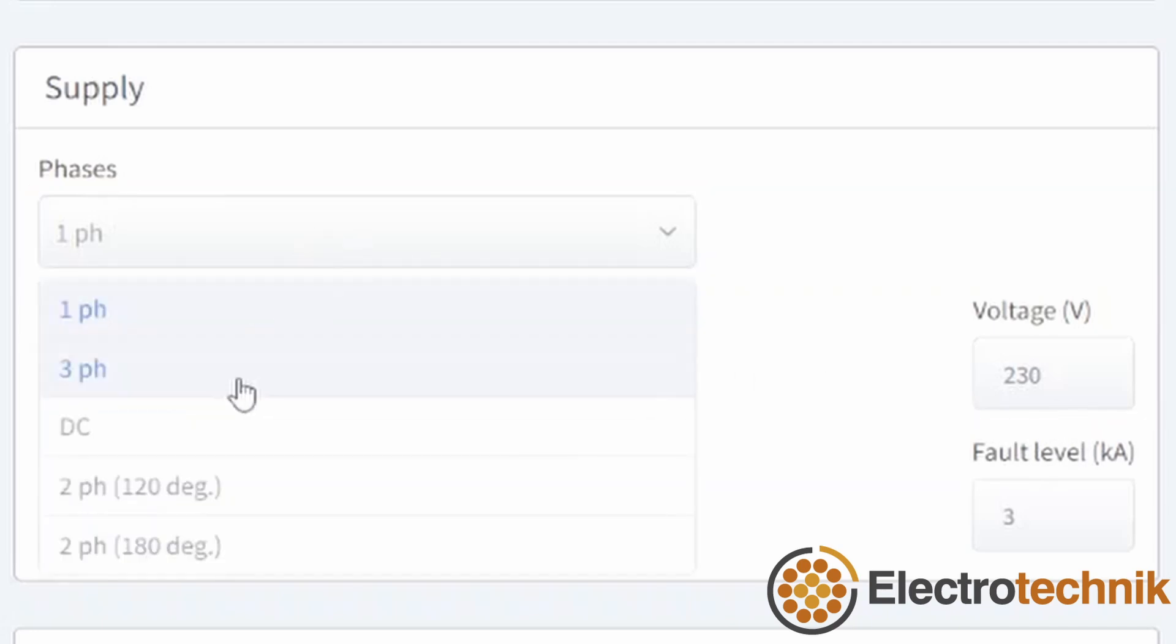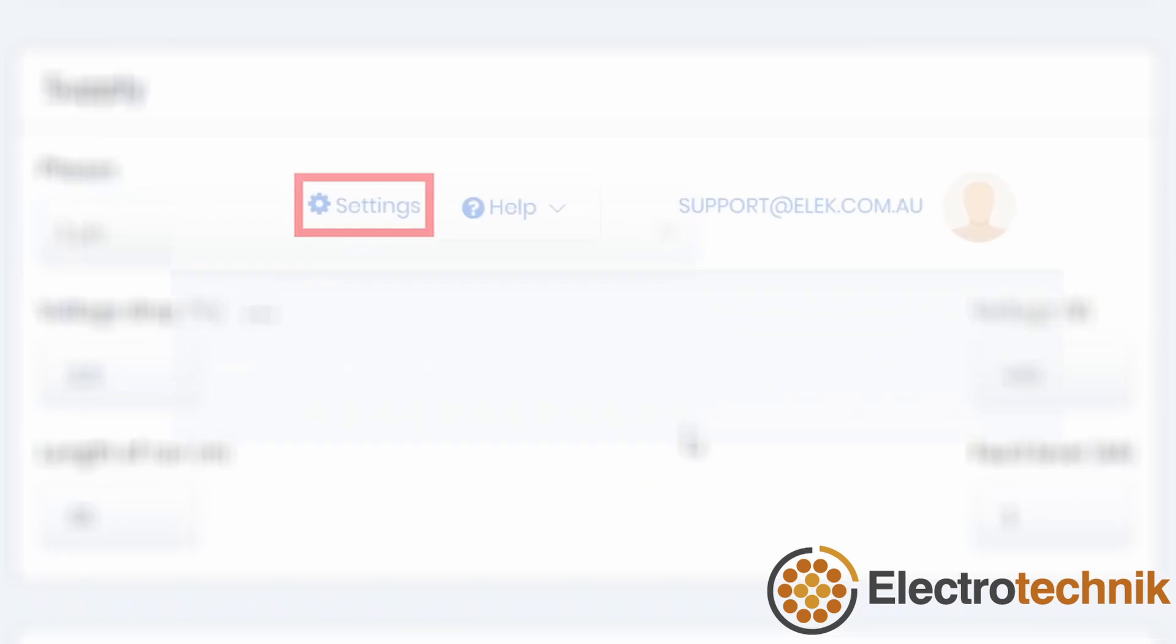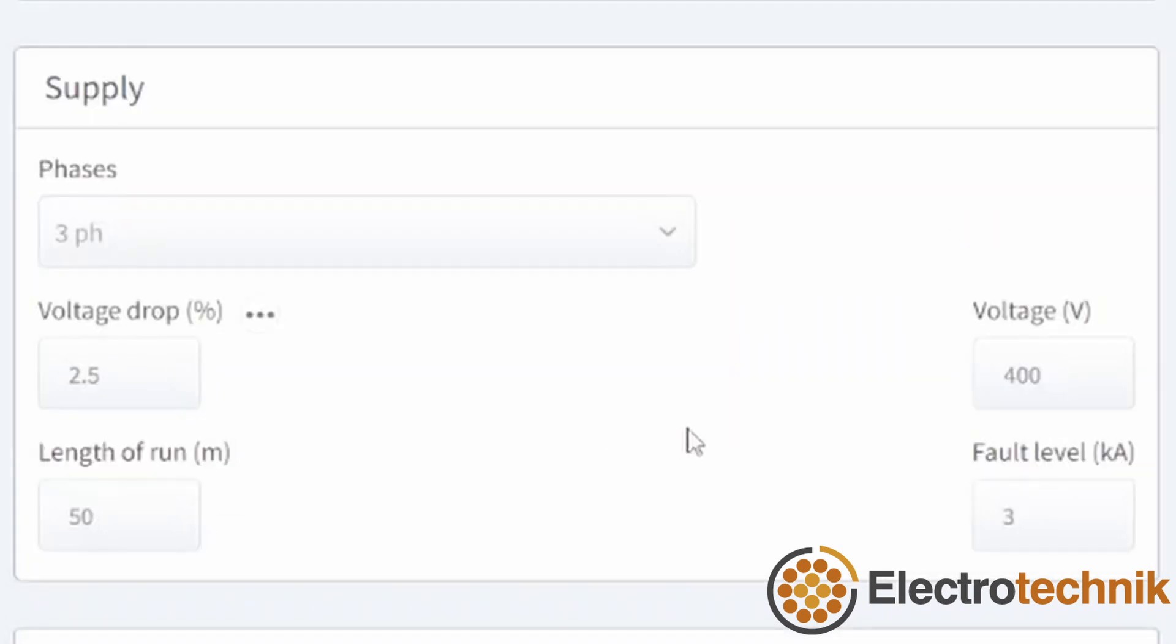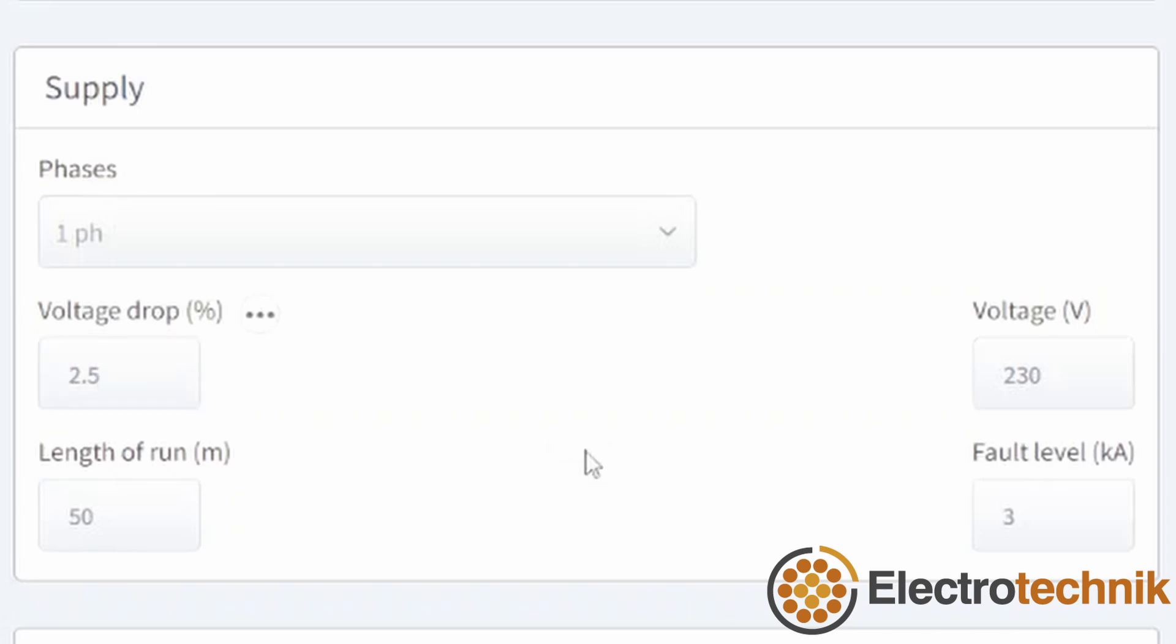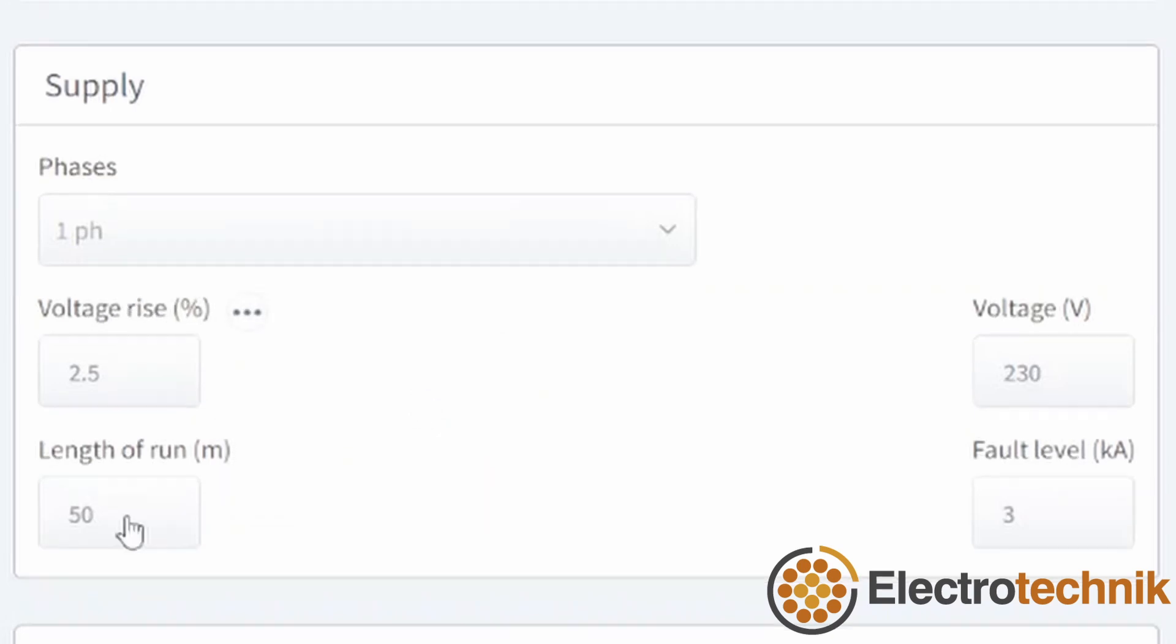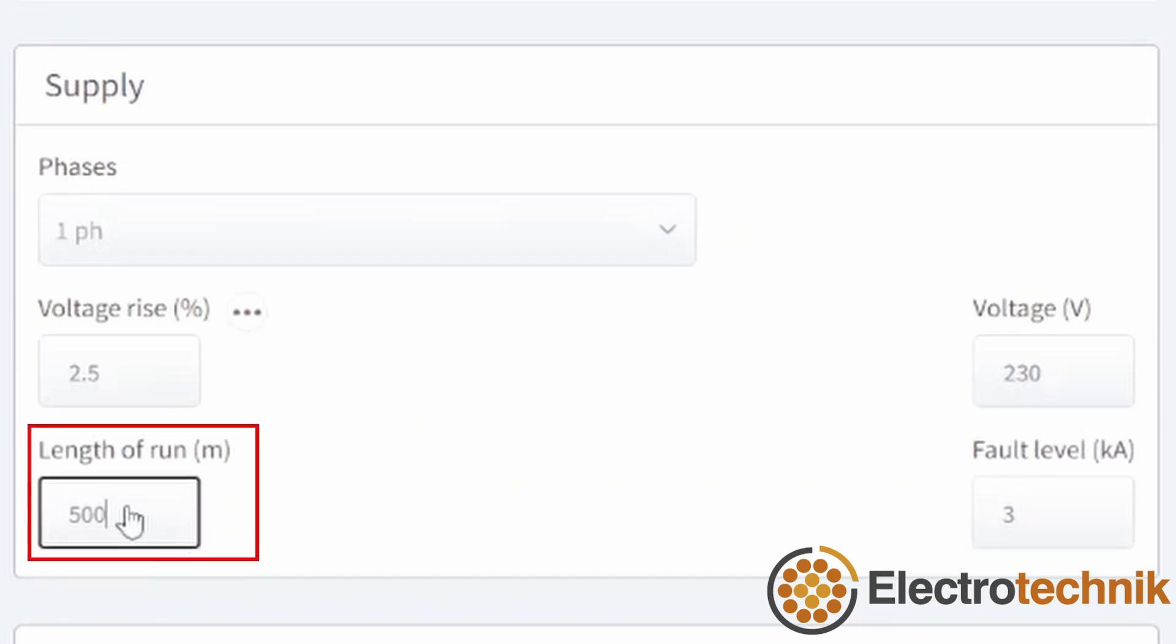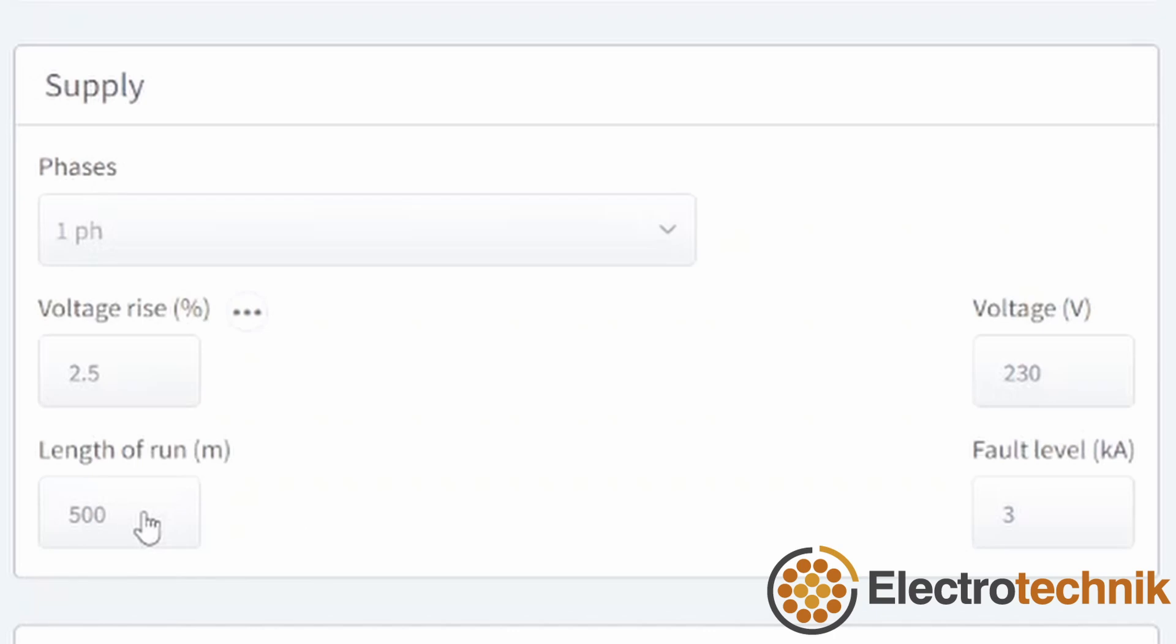Additionally, these default voltages can be changed in settings. Voltage drop is entered as a percentage of the supply voltage. This is the maximum allowed voltage drop and changing this input may determine the final cable size. You can switch between voltage drop or voltage rise calculations. This doesn't really change the calculations but affects the wording of the load current and the wording in the report. The length of run is the distance from the cable supply to the load which affects the voltage drop calculations. You can enter very long cable runs into the software.